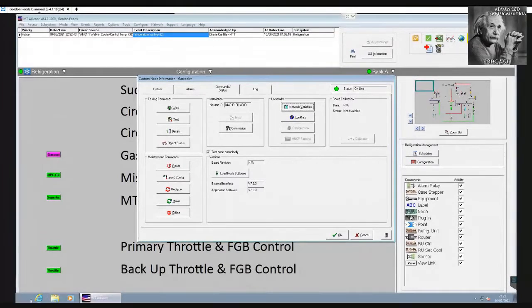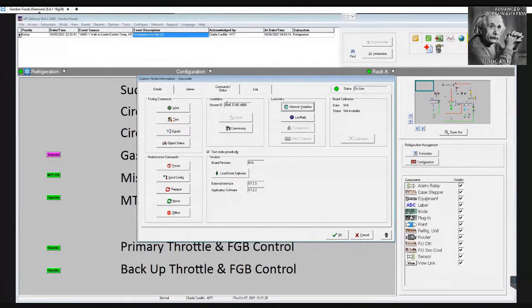We'll get to this node and hit this install button, and then you'll see a bunch of numbers and letters flashing at the bottom of the screen. That's how you initially bring this online, and all the parameters are flashed to this simply by pushing that service button. And here's your Neuron ID. If I ever have to recommission, I can do it from here, or send configuration - I'll show you a report later that tells you why you might want to do this.